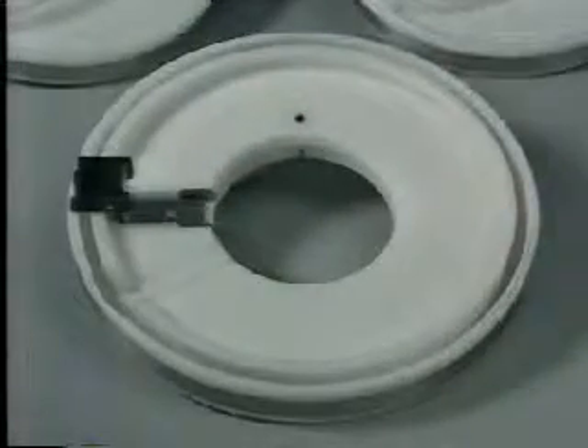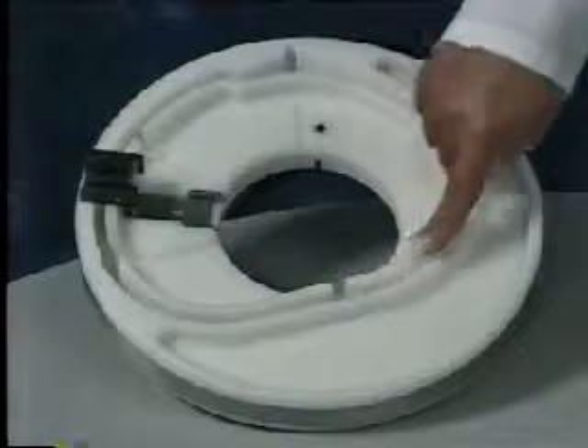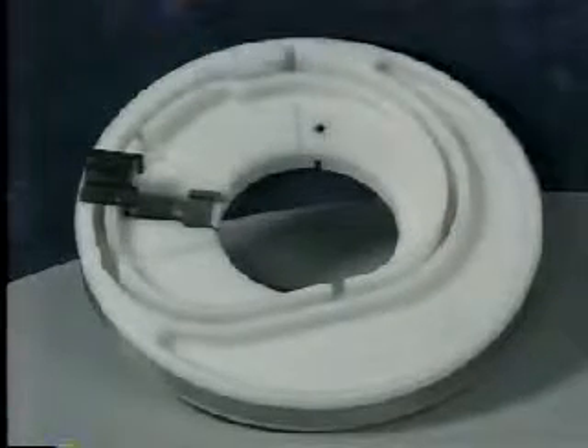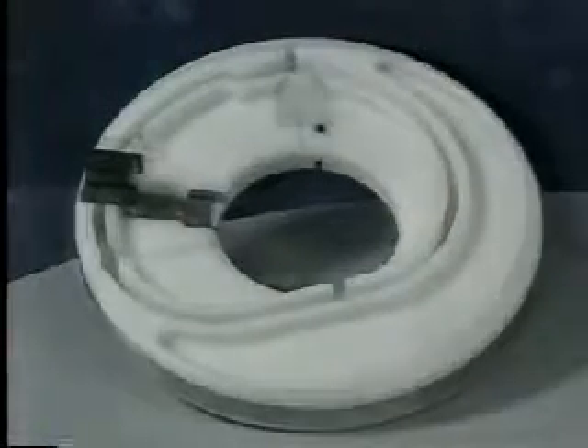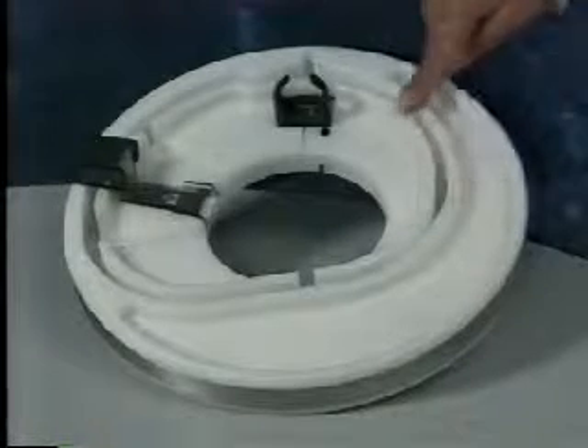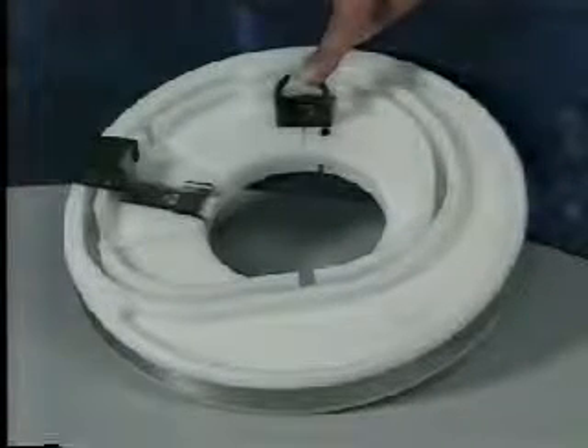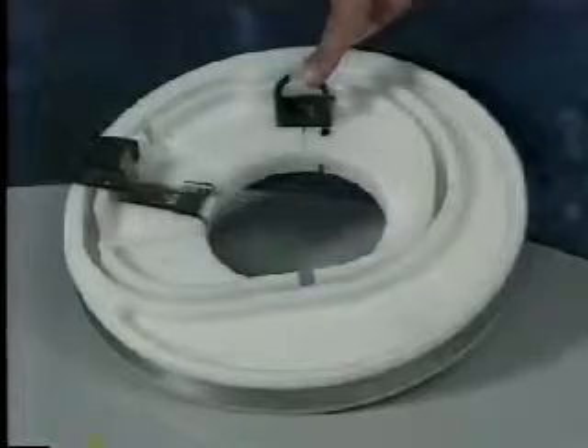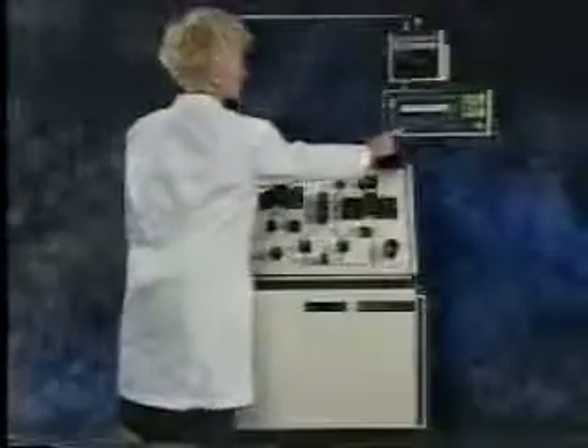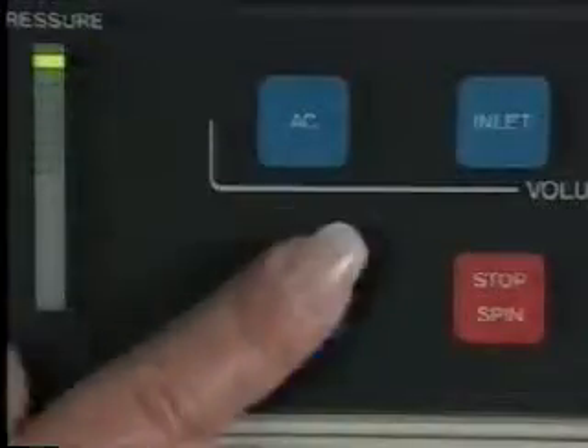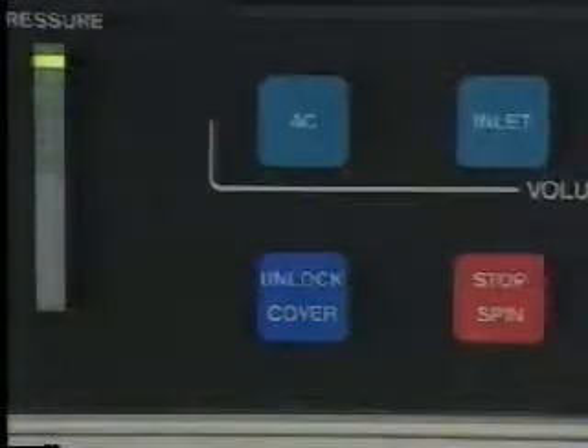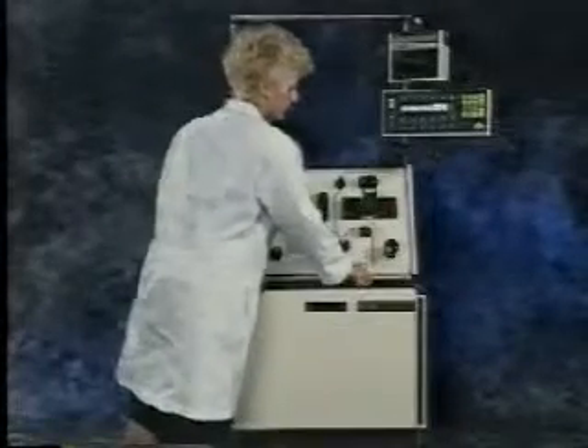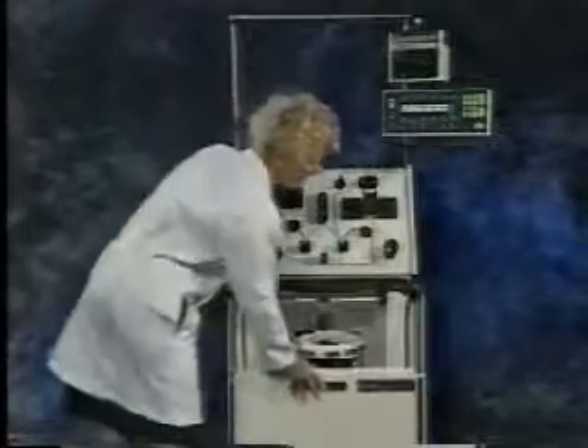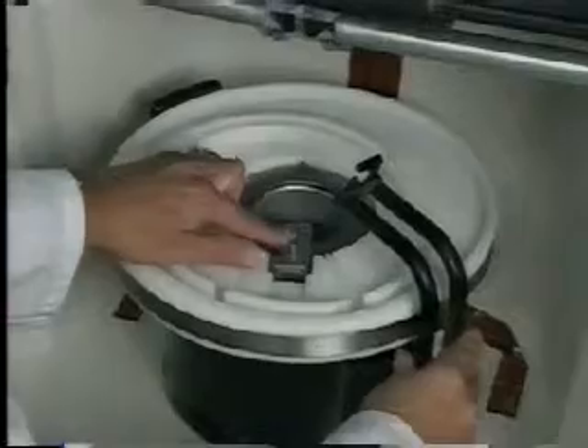Some procedures require the single-stage filler. Standard ELP procedures require the dual-stage filler. You will need the dual-stage filler with the LRS chamber bracket. To check the filler, press the Unlock Cover key. Slide the centrifuge cover back and lower the centrifuge door. If a different filler is in place, remove it as follows.